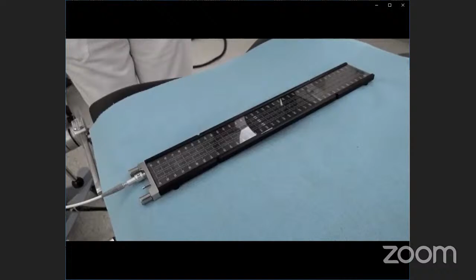There is a special tool with a glass window and a millimeter scale. The transfer tube is connected to this tool. The source is driven out to a position of 200 millimeter. And here we can see that the source at the end of the cable is stopped exactly at the 200 millimeter mark, meaning an accurate positioning.